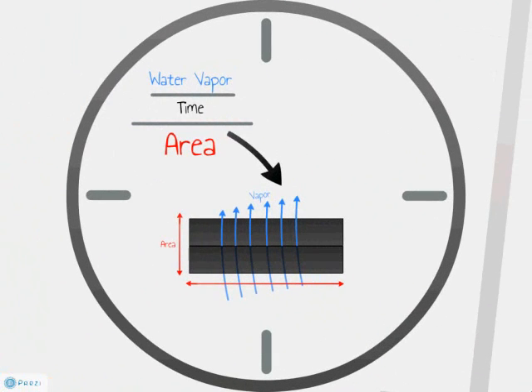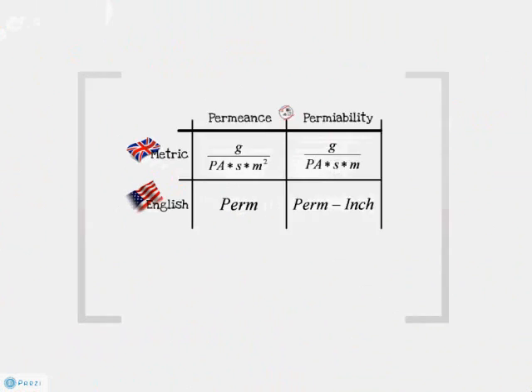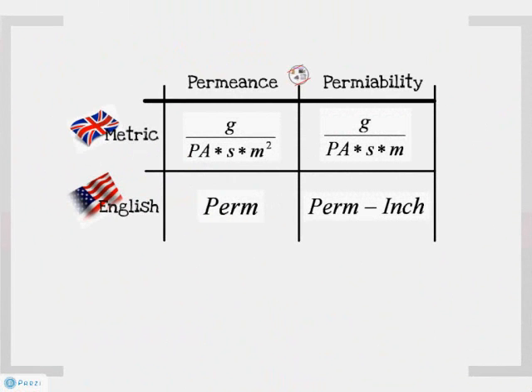Water vapor permeance is the time rate of water vapor transmitted through a unit area of material, induced by unit vapor pressure difference between the two exposed surfaces of the material. In the construction trade, this term is generally expressed as perm in English measure, or in grams per pascal times second times meter squared in metric.